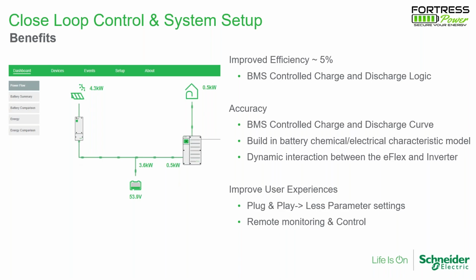Second is accuracy. The BMS controls the charge and discharge curve. We're all familiar with 3-stage or 2-stage charge and discharge, but is that the best for lithium batteries? Not necessarily - it always depends on temperature, load, and charge and discharge rate.